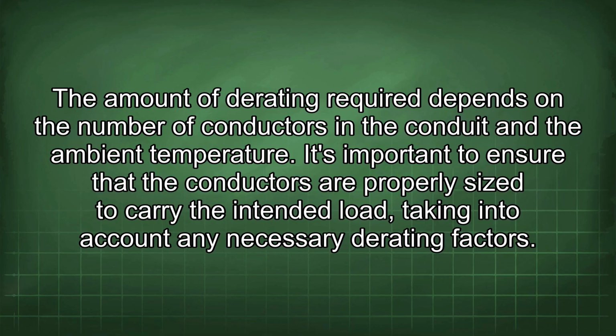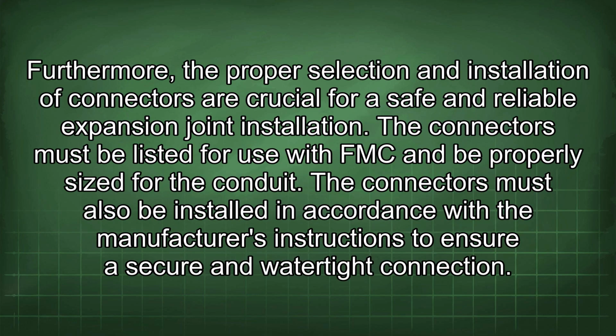derating factors. Furthermore, the proper selection and installation of connectors are crucial for a safe and reliable expansion joint installation. The connectors must be listed for use with FMC and be properly sized for the conduit. The connectors must also be installed in accordance with the manufacturer's instructions to ensure a secure and watertight connection.